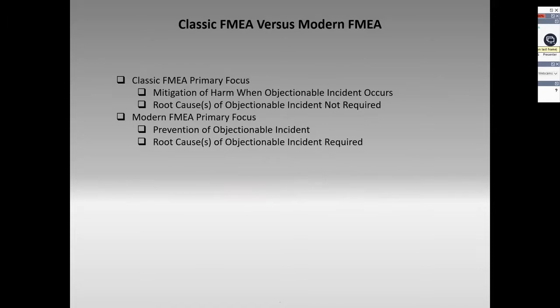Now, historically there's been what I call the classic FMEA approach. The original FMEA is what we call failure mode effect and criticality analysis. What would happen is the whole focus - they'd spend all this time identifying the failure modes, then take each failure mode and identify all the potential effects and their harms, and then try to mitigate those harms. It was interesting reading some of those FMEAs that there was very little time spent on the actual root cause of the failure that led to the exposure to the harm.